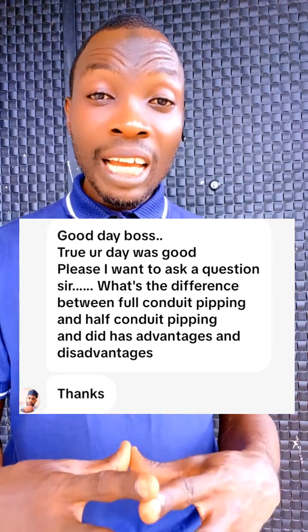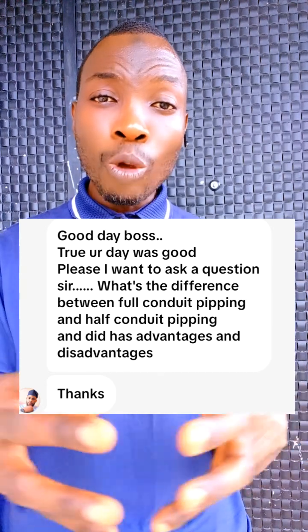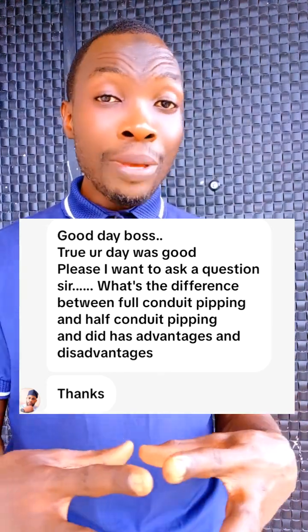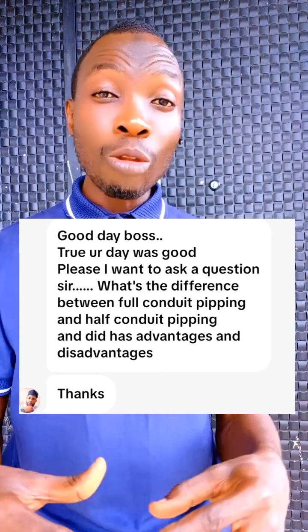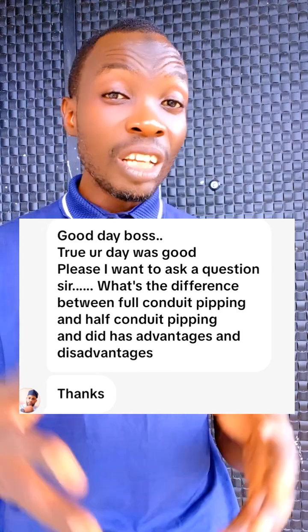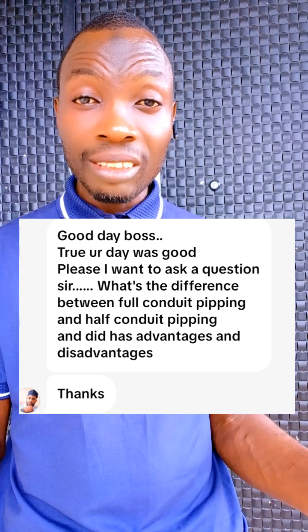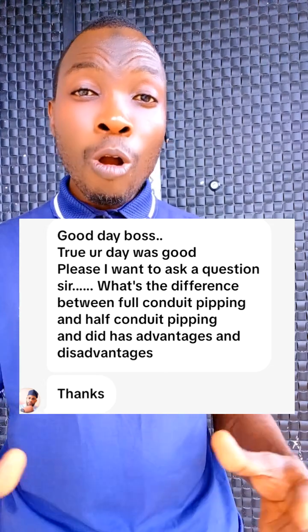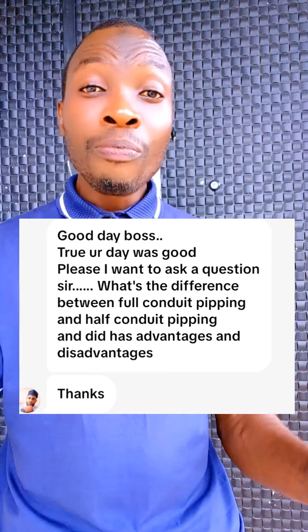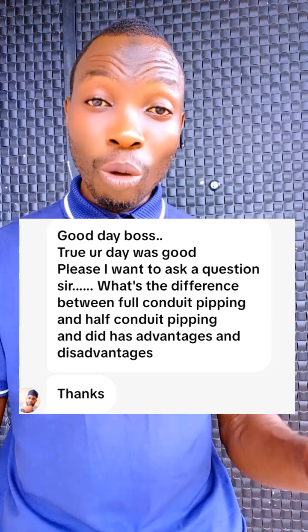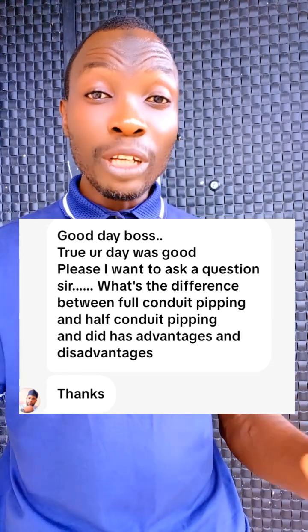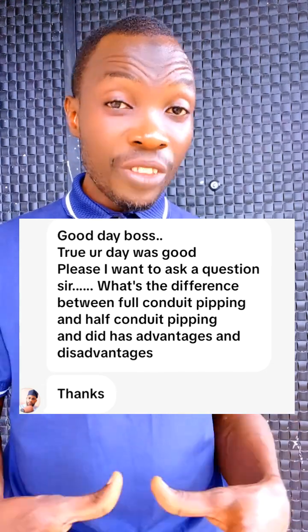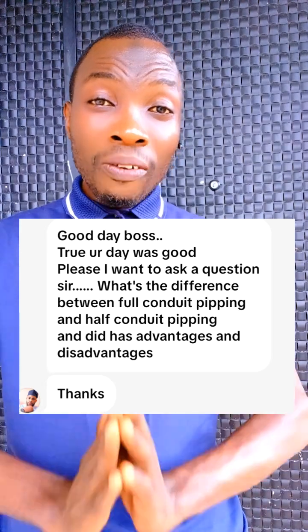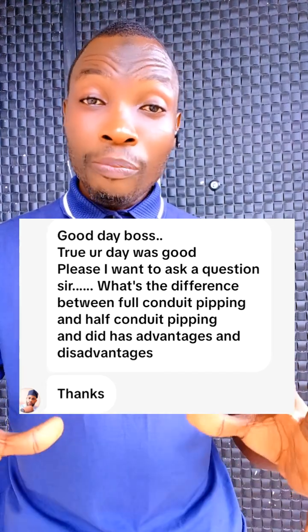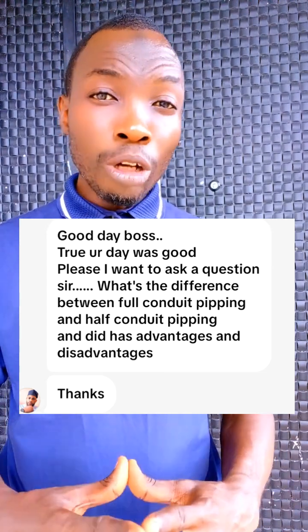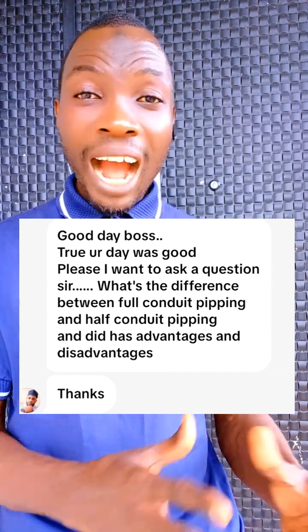The temperature surrounding cables. If there are so many choked up in the pipe, the ambient temperature rises, and this in turn affects the insulation quality of the cable. When cables start carrying current, their temperature also rises. Coupled with the temperature of their surroundings, it makes the temperature surrounding the cable so high, which can eventually break down the insulation property of the cable. So, provided you keep reasonable ambient temperature and you observe the space factor, full conduit remains the best over half conduit.